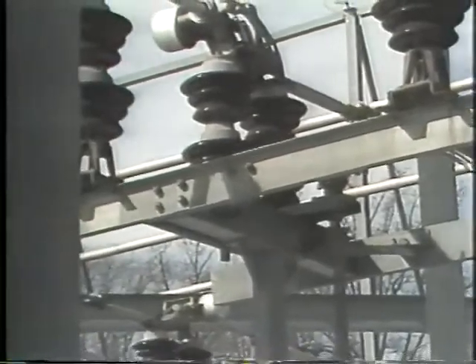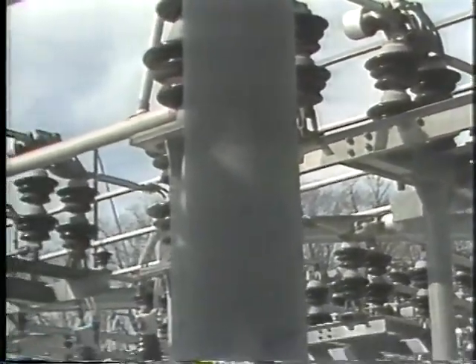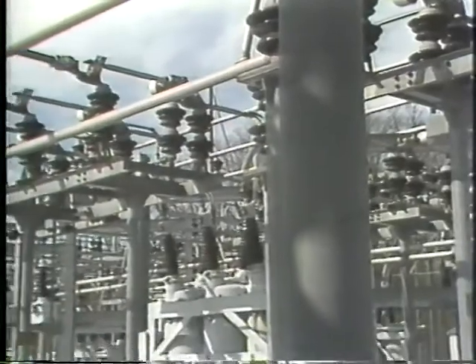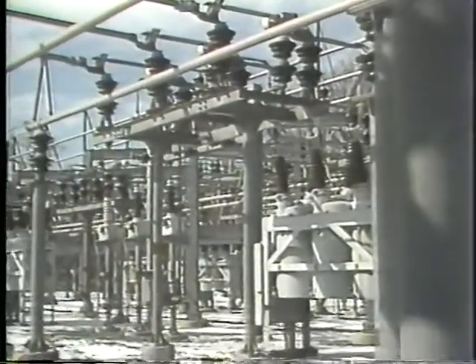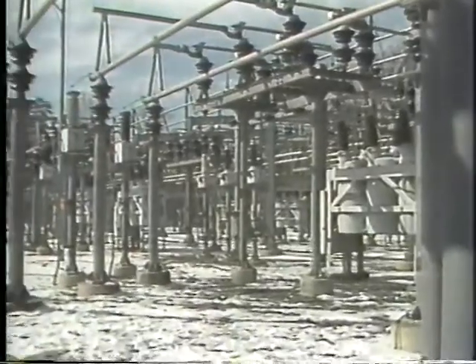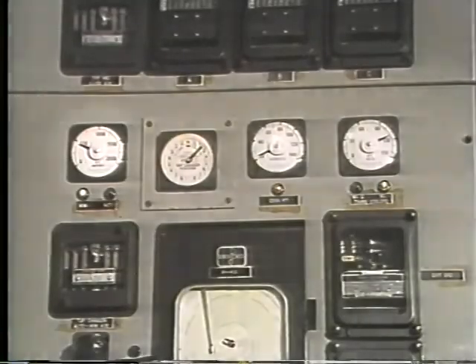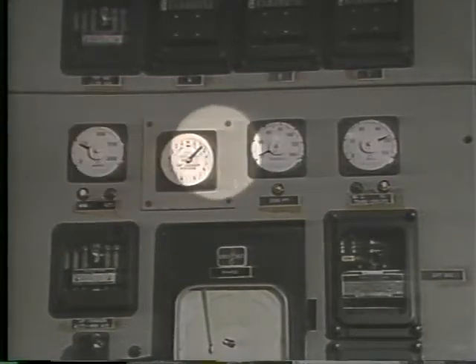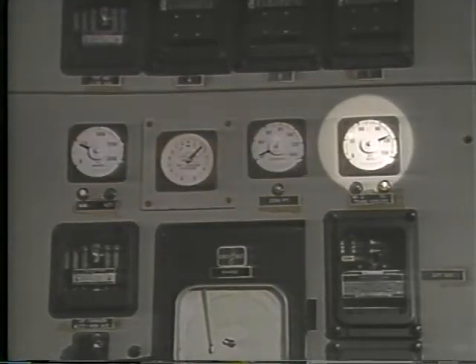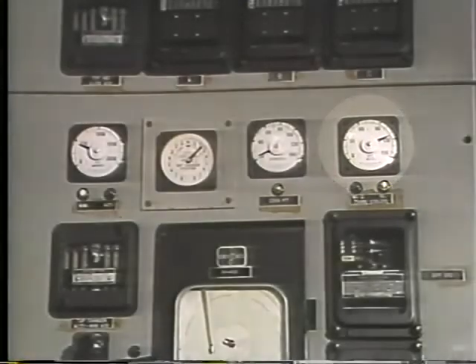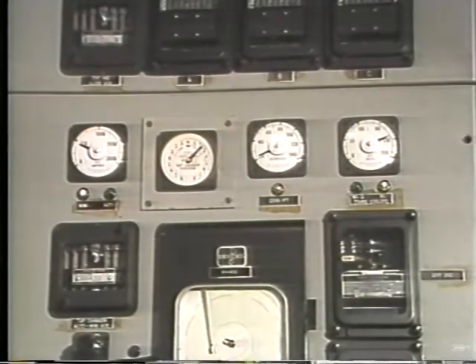There are a few other devices at any large plant that'll surprise you as well. As an electrician, you know something about meters, right? But have you ever thought about how you'd take a reading on a 14 kV line? On high voltage, high current lines, you just can't go around with a multimeter and directly measure everything you need to know. On equipment like this, there are built-in transformers that reduce the current or voltage to levels that meters can handle. Current transformers feed ammeters, and potential transformers supply the voltmeters. If you ever have to test or replace meters like these, you'd better learn the difference.